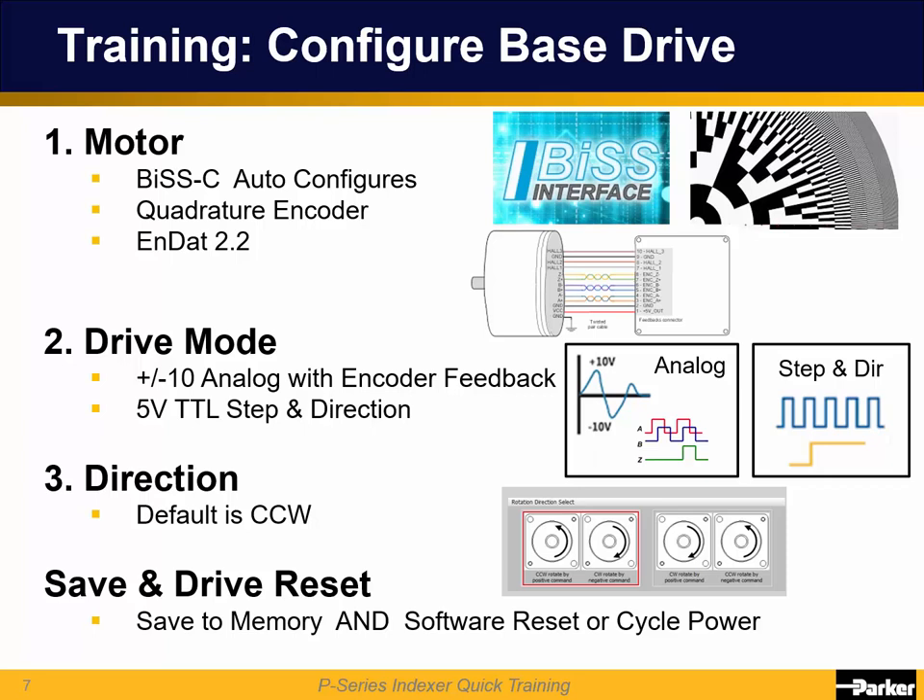The default is counterclockwise looking at the motor shaft as positive. If replacing an older Parker Aries drive, you'll need to switch the direction to clockwise as positive. Then save to non-volatile memory and do a software reset or just cycle power.